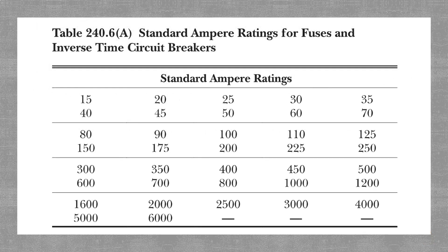Here is Table 240.6A — standard ampere ratings for fuses and inverse time circuit breakers. This table is very straightforward with no figuring or cross-referencing required; it's simply a listing from smallest to largest of standard ampere ratings. Going back to our earlier example: if we calculated needing 22 amps of overcurrent protection, we'd look at this table and see that 22 amps is not a standard ampere rating. So we would either go down to 20 amps or up to 25 amps depending on circuit type. The table goes from 15, 20, 25, 30, all the way up to 4,000, 5,000, and 6,000.